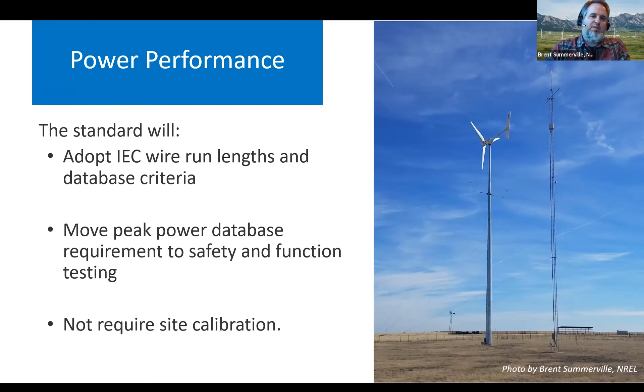And further optimization is not requiring a site calibration. These are small turbines. The Met Tower is not that far away as compared to large rotors. And so we thought, we may lose a little bit in accuracy, but save some in testing costs by not requiring that site calibration, where you put an anemometer where the wind turbine will be, and you measure wind there and at your Met Tower for a while and come up with a correlation factor, which typically came out to be something like 0.98 because they're fairly close together. You still have to do a terrain assessment, but not a site calibration.